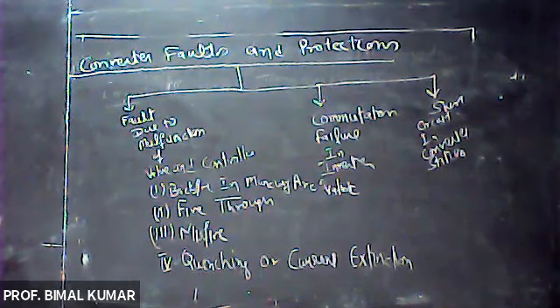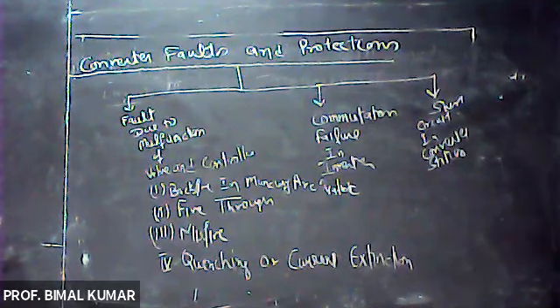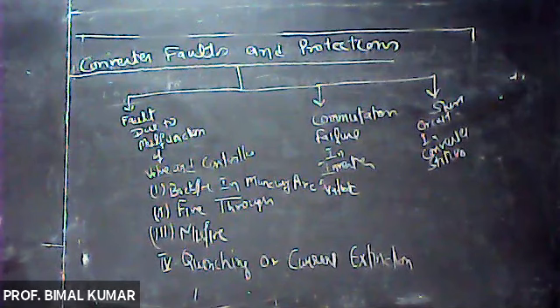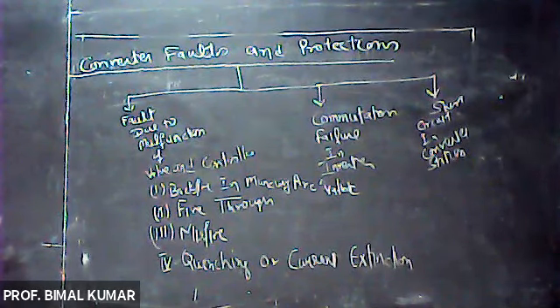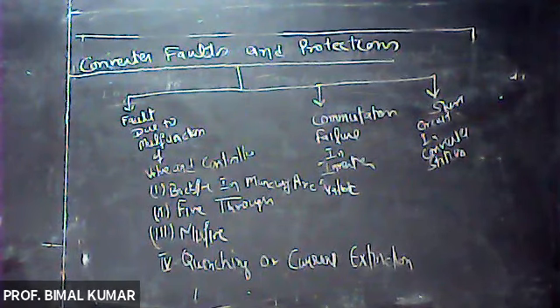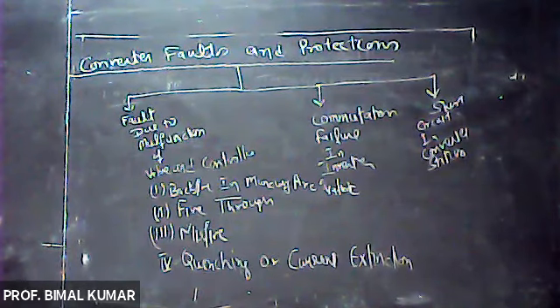Arc back in mercury arc valves is of a random nature - it occurs randomly. This is a non-self-clearing fault and results in severe stresses on the transformer winding, as the incidence of arc back is common.